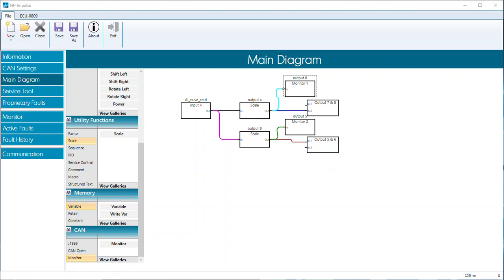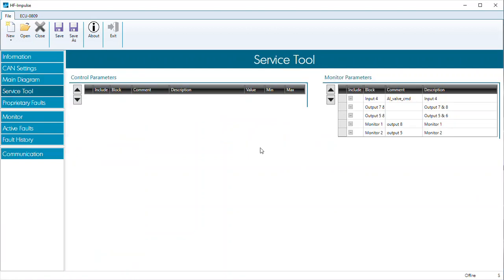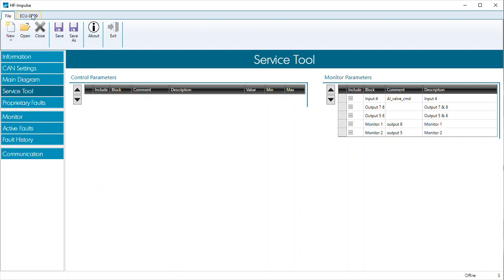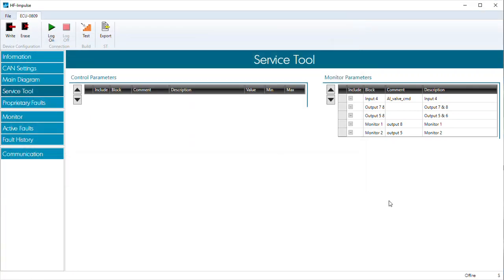So this should be our configuration. Let's go ahead and create the service tool. Coming over to the service tool section, I don't have any control parameters yet — that will be in video two. But our monitor block shows input four with a comment of AI valve command. Seven and eight don't have any comments added. Monitor one and two are output eight and output five. I'll come over to the ECU 0809 tab and hit export — this will allow me to create a service tool. I'll go ahead and label it service tool.